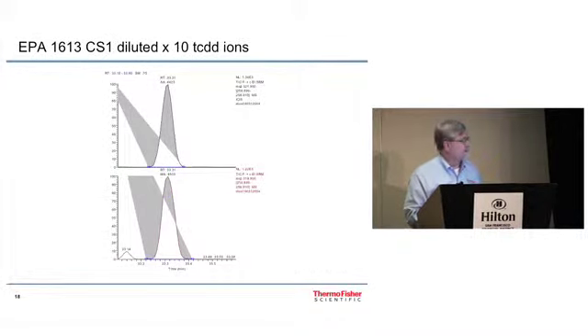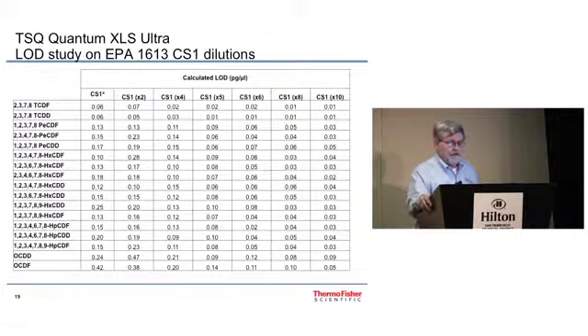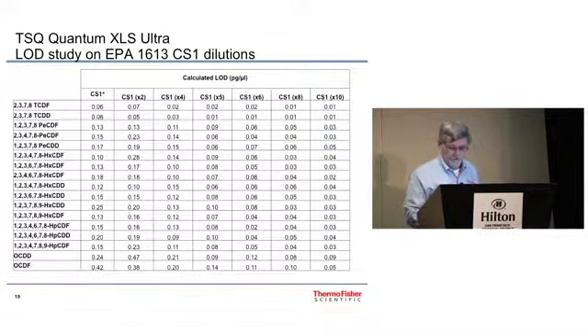Here's a close-up of the tetra, diluted 10x. Now, why is this important that you can see at lower concentrations than you run your standards? Because if you can see lower, your detection limits are lower. Here we're taking the CS and run multiples and then diluted it down 2x, 4x, 5x, 6x, all the way down to 10x. And you can see how the LOD changes and gets lower.